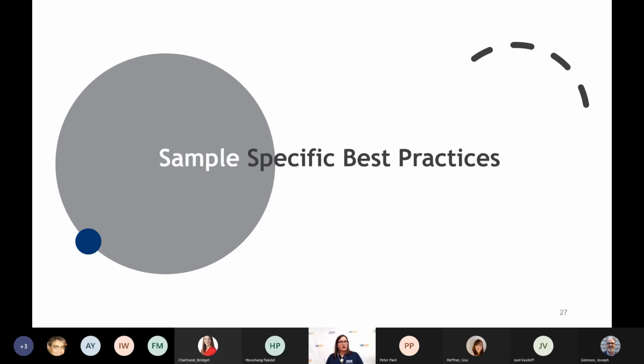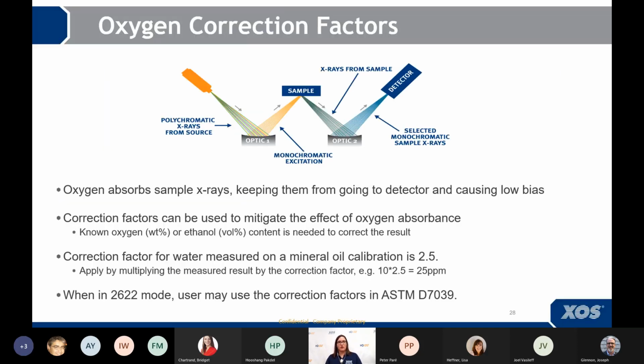We talked about correction factors earlier and why they might be used. Let's talk about oxygen. If you run an oxygenated sample on a mineral oil calibration, you are going to see a low bias. This is because oxygen absorbs sample X-rays. Those sample X-rays never go to the second optic or to the detector, and you get this low bias. You can use correction factors to mitigate the effect of oxygen absorbance.